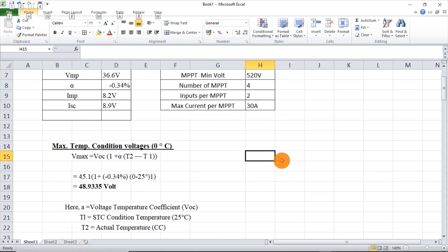Let's see how to calculate the maximum number of modules to be connected in series in a particular string. For maximum, the formula is: Vmax = VOC × (1 + α × (T2 − T1)). Here VOC is the open circuit voltage of the module, and alpha is the temperature coefficient. T2 is the actual minimum temperature — we have taken it as 0°C — and T1 is the STC, standard test condition temperature, normally 25°C from the datasheet. Giving all these inputs, we get Vmax = 48.9V.